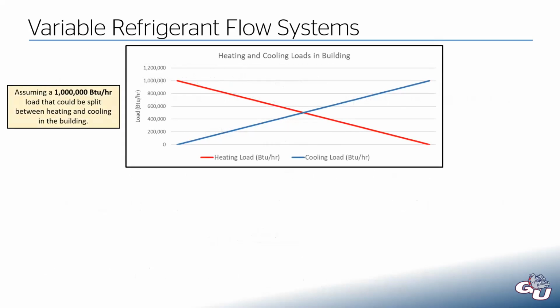To help illustrate this a little further, let's say we have a scenario where this is an oversimplification, but I think it helps illustrate what's going on. So let's say at any given point in our building, we can be heating dominant, where we have a very high heating load, where basically everything is in heating, nothing is in cooling. Or we could have somewhere in the middle, where we still have some cooling load and some heating load. Or we could have a scenario where basically everything's in cooling, nothing's in heating. Throughout the year, we could be anywhere along this line at any given time. In the summer, we're going to be closer to this side. In the winter, we're going to be closer to this side. And in the spring and fall, we're probably going to be somewhere in the middle here.